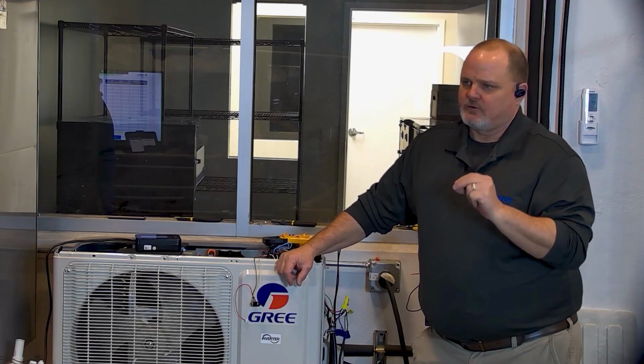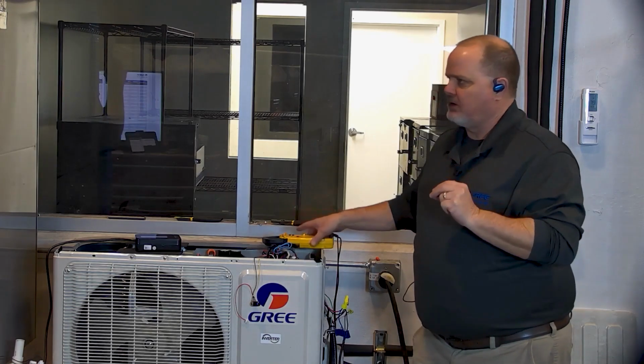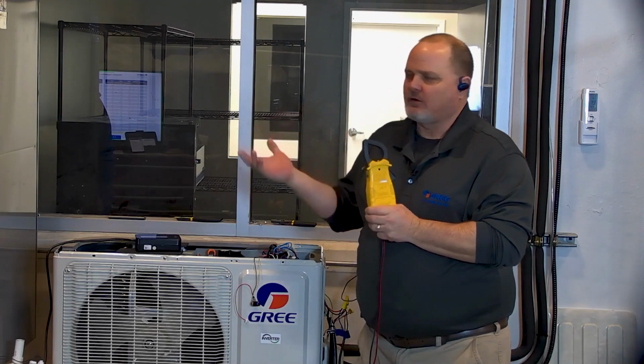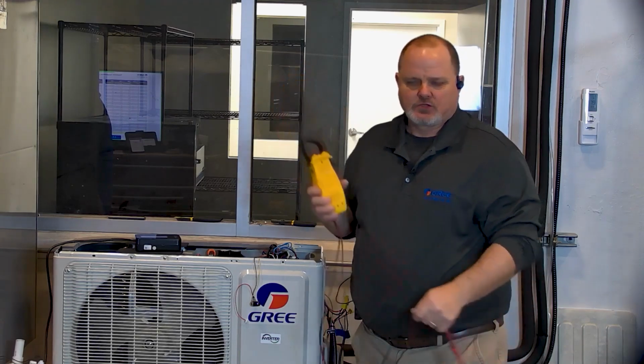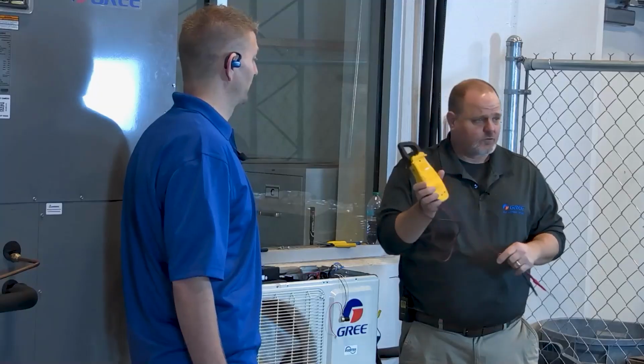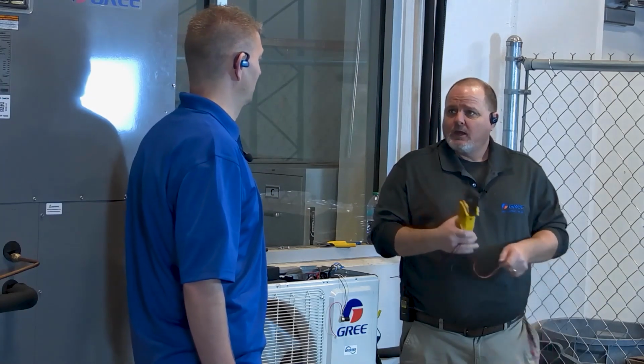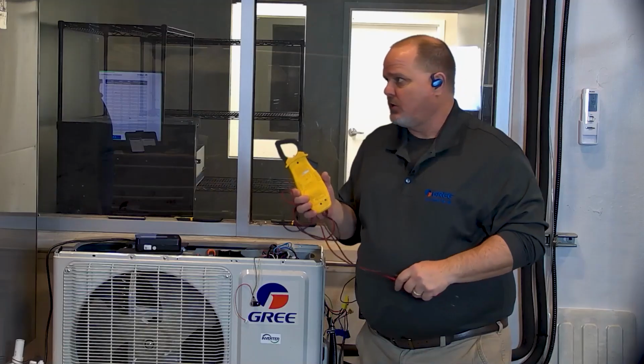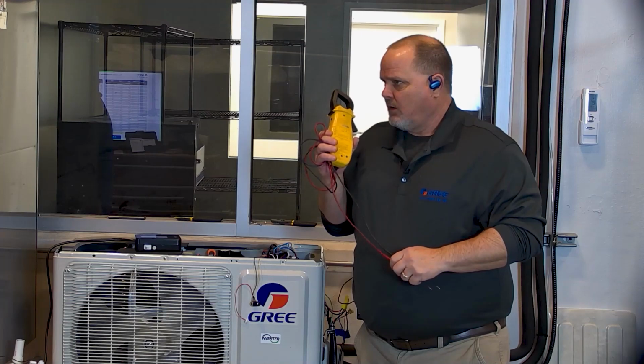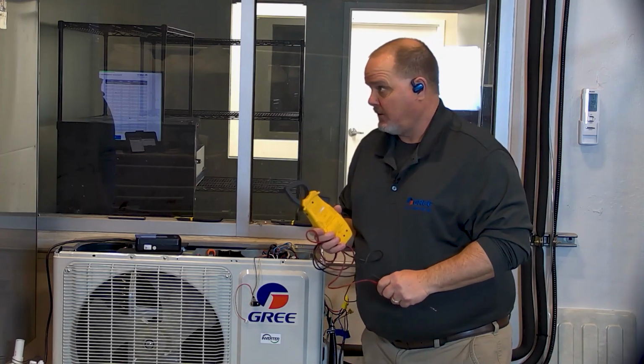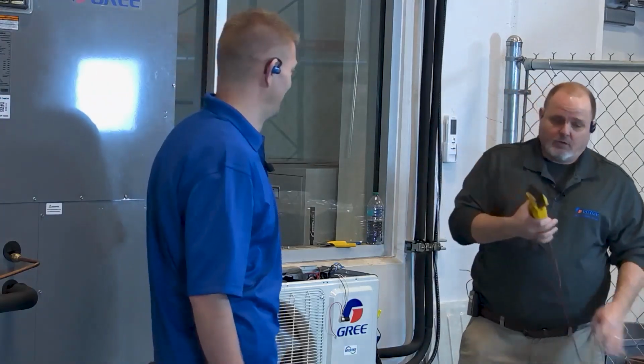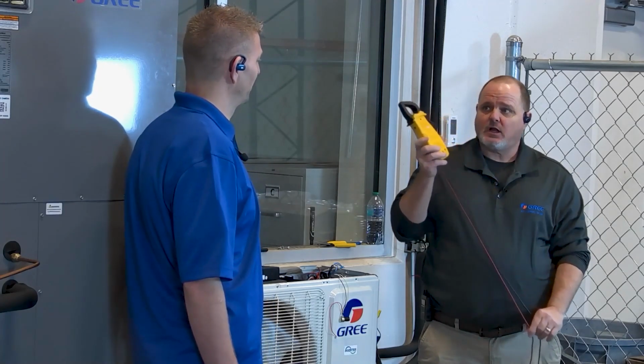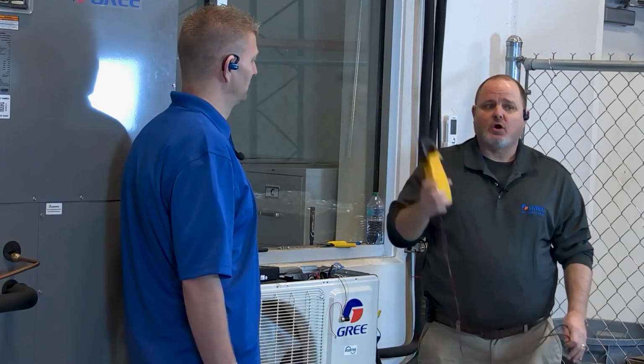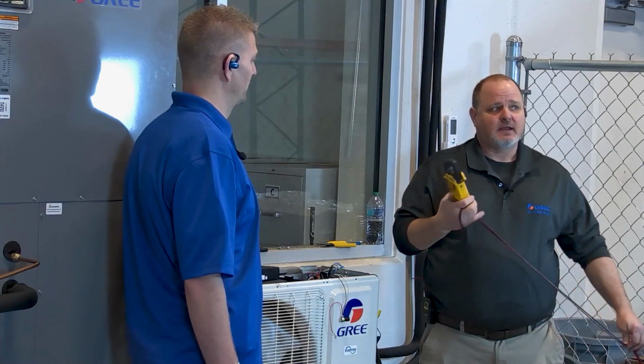What you've got to keep in mind is you're testing that with your meter and the power source of that meter. Whether you've got a regular volt-ohm meter using AA batteries, which actually has more current capability than this meter with a little 9-volt battery, you're using batteries. You are not using 230 volt power. It also matters if your battery is low or not. So what I'm telling you is that you could have a voltage bleed through the insulation class of that 14-4 wire that is causing your E6 communication error, and you cannot detect it with a normal meter.